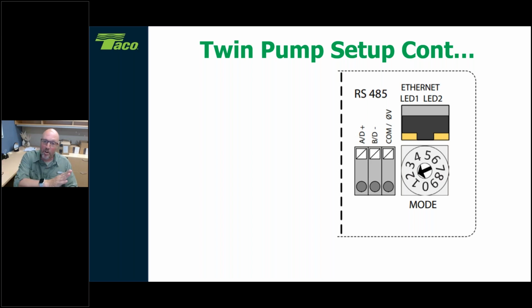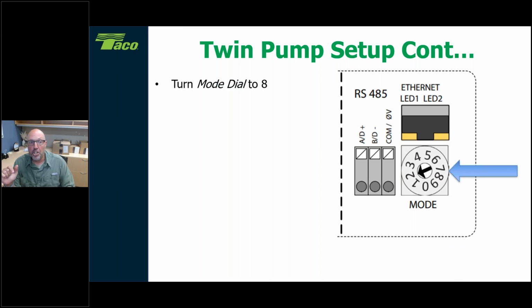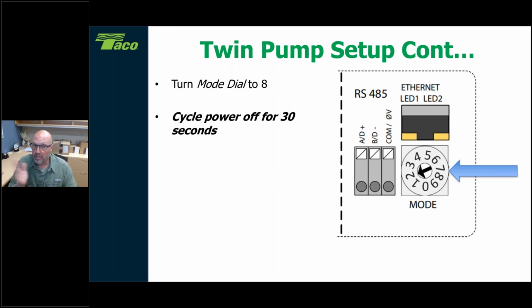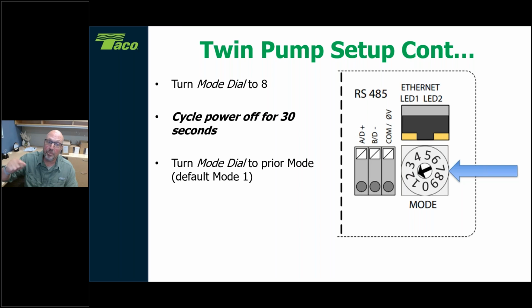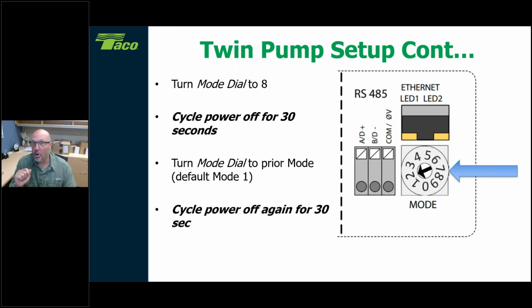All right, we did that over there. Here's where you have to get into the mode dial. You do have to change the mode dial, so you're going to have to power these pumps down. So you're going to turn the mode dial to 8. It doesn't stay there. Cycle the power down. Now when it powers back up again, you turn the mode dial to 1. We start going into that mode.